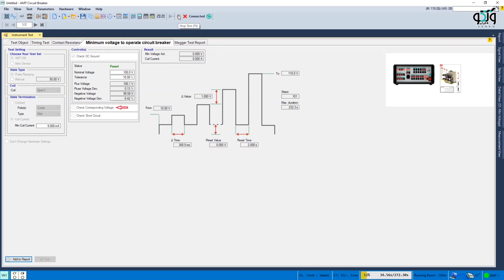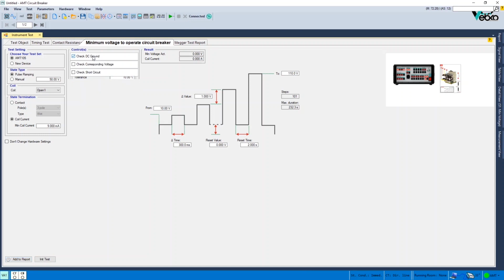Check corresponding. Since in some electrical installations multiple voltage resources are used to supply different equipment, it may be necessary to test the positive and negative potential of the existing cables so that no mistake occurs in terms of positive and negative potentials. For this test, the maximum voltage allowed between the two poles of the two resources is entered in the voltage drop field. To be precise, suppose that the two resources A and B are being used to supply the equipment. Normally, there should not be any potential difference between the positive A and negative B sides of the resources. If there is any potential difference between these two, it means that they both belong to the same resource and can be used to supply the equipment.